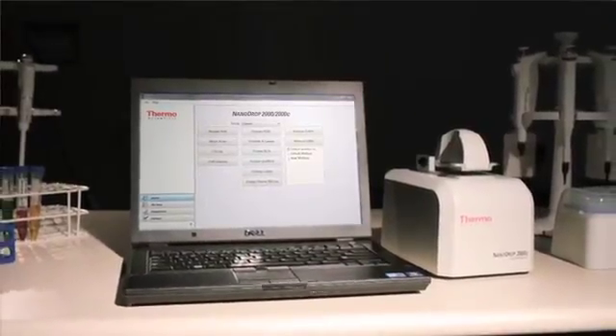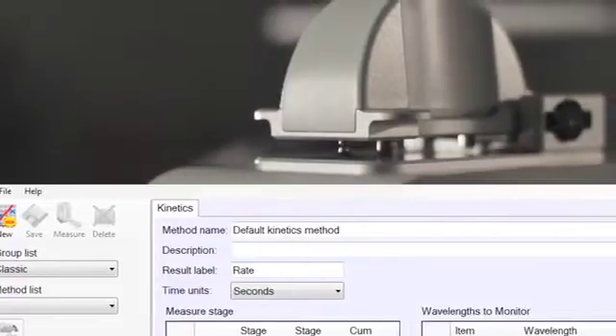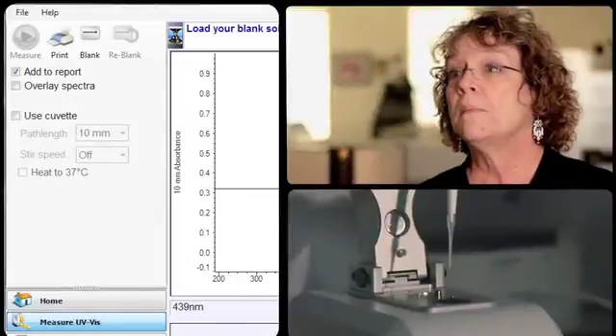However, there are some fabulous upgrades and differences. Number one, the ability to do kinetics. The ability to define custom methods. The ability to have expanded spectrum. The ability to monitor multiple wavelengths in the UV-Vis application. You can define as many wavelengths as you would like.